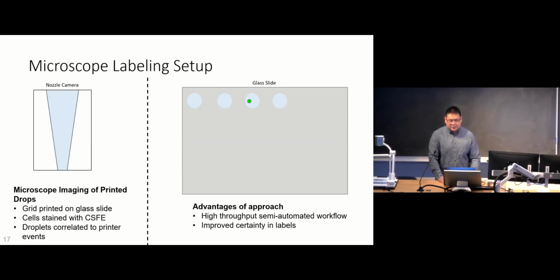The slide is imaged under fluorescent and bright field microscopy with our Nikon TI2E microscope. And imaging of the printed grid allows for correlation of the microscopy images to our instrument's captured images. Using this approach, due to the cell encapsulation process being governed by the Poisson distribution, the most commonly occurring class of no cells being in a droplet can be rapidly identified through a lack of fluorescent signal. Droplets of interest containing fluorescent signal can then be investigated manually and used to determine the correct class.